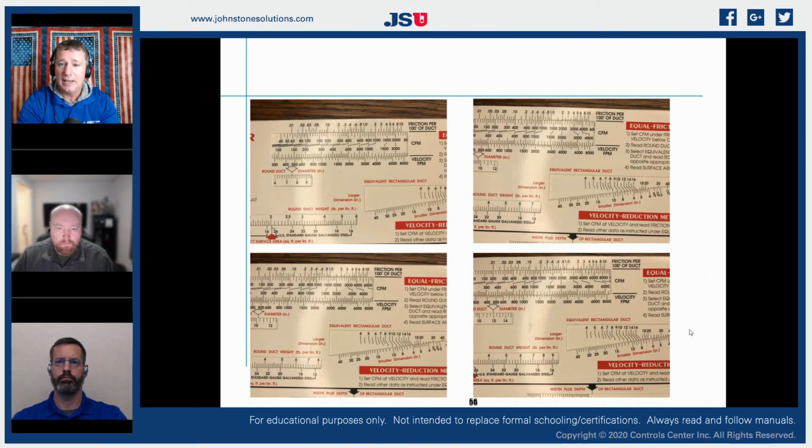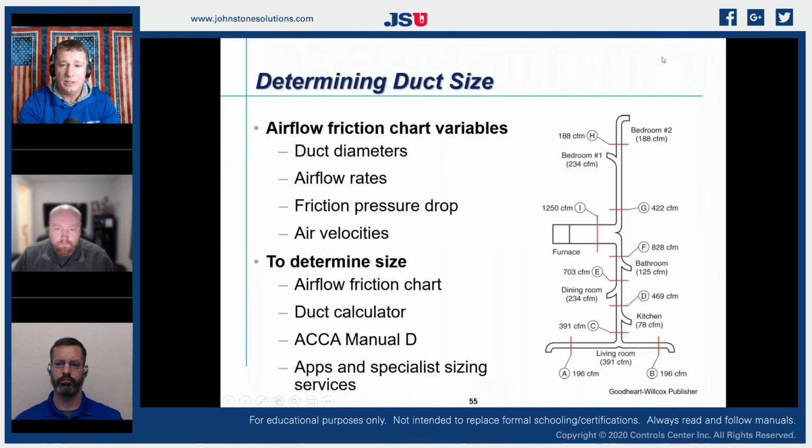So when I get to that point, then I need to be able to take off to my 2 additional side runs. And at this point, I can do one of 2 things. Looking at this, it's showing that I'm actually using a duct transition, which means I'm going to continue using my 8-inch rectangular duct to feed down towards my drops, or I can do a round on this. So let's look at both of them. So that means that 8x12 runs to the end into the living room, and then I'm going to branch off and I'm going to do one of 2 things.